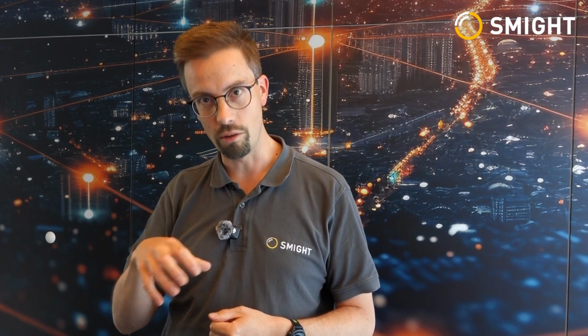The other thing to note is that 70 degrees is often mentioned, but the reality is somewhat different. Even when you have a distribution cabinet in the middle of summer, in the sun, with lots of current flowing, the fuses might be hot. Yes, it's very hot in there, but heat rises, and all of our devices are installed down at the base of the distribution cabinet where it's much cooler. The actual measurements taken in studies of this type have shown that in the area where we're installed, you don't tend to get above 50 degrees even in extreme situations. So it's maybe a bit of a nuanced answer, but that's really the reasoning behind it.